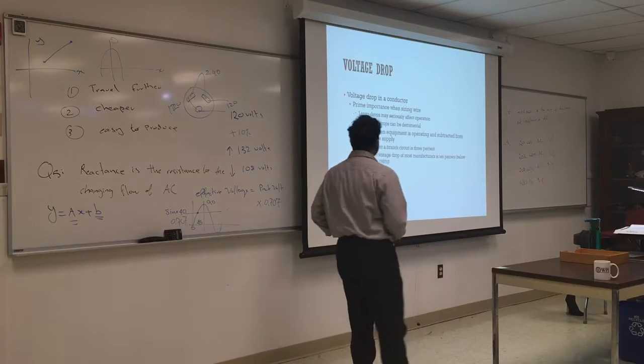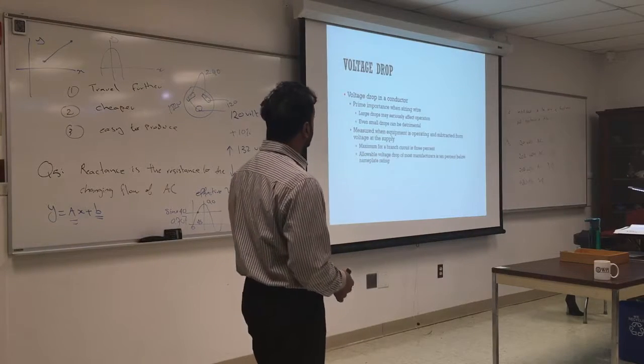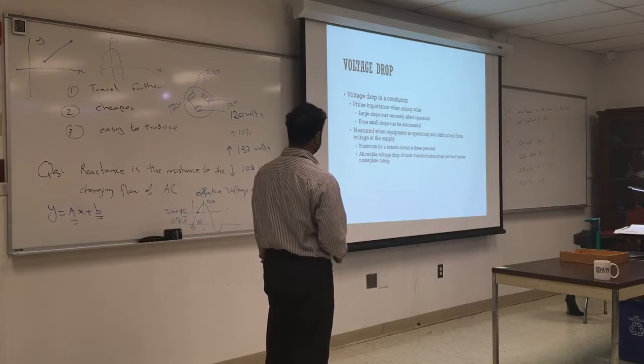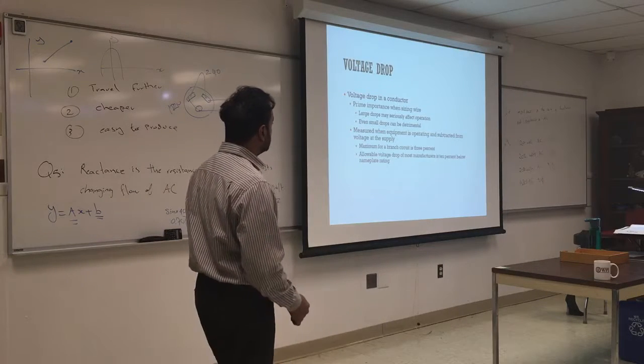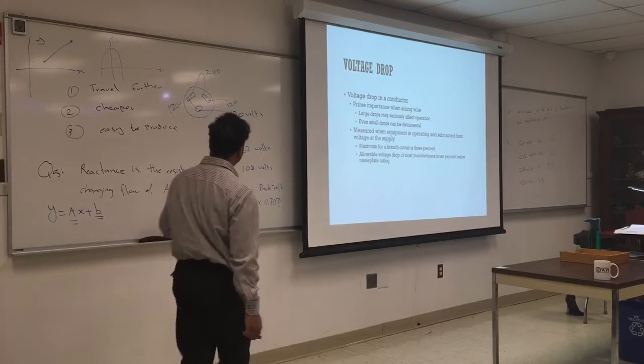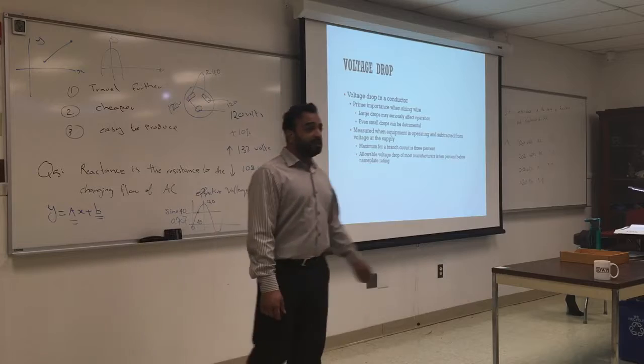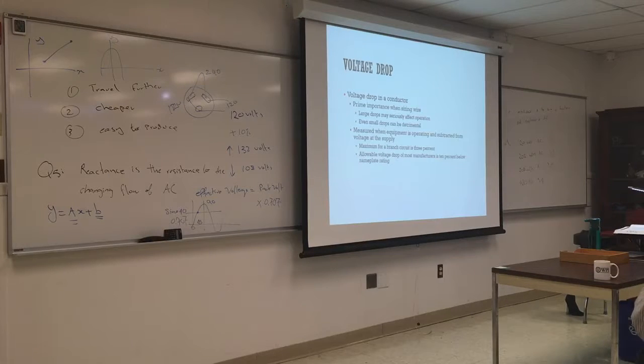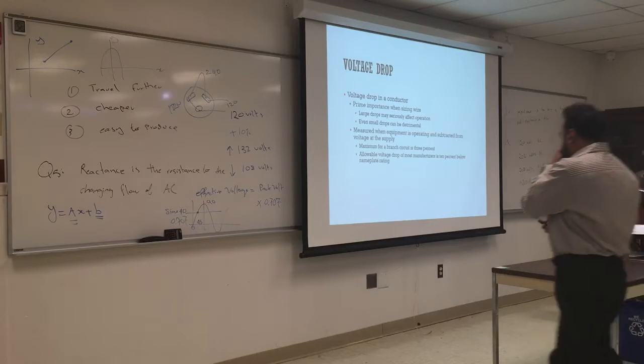Voltage drop in conductors, that's again the main thing we have to be worried about when we do wire sizing. A large drop may seriously affect operation, and small drops can be detrimental. And we say these drops, our limits are plus or minus 10%. And why would that affect performance? If you have a compressor that requires a lot of voltage, and the capacitor that turns on the motor is required to be charged at a certain time. And the more electronically built the equipment, the more sensitive it is to changes. Like these mini splits, they're very, very finicky, require very sensitive operation and a certain amount of voltage. So that's something you have to think about.